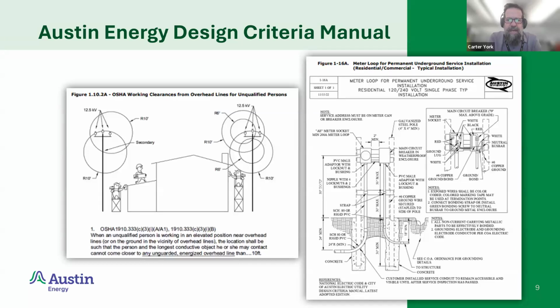A couple of things I pulled to show you: on the left is a figure for working clearances from overhead lines for unqualified persons — these are OSHA working clearances. It shows the pole, with the three conductors at the top, and circles representing radial clearances from those conductors that need to be observed to provide safety for anyone working out there.